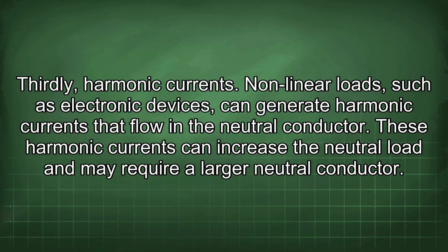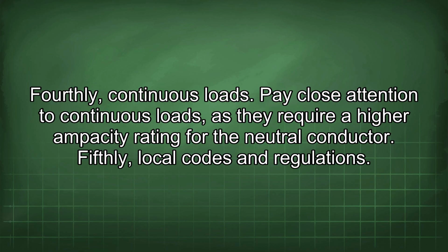Thirdly, harmonic currents. Nonlinear loads, such as electronic devices, can generate harmonic currents that flow in the neutral conductor. These harmonic currents can increase the neutral load and may require a larger neutral conductor. Fourthly, continuous loads.